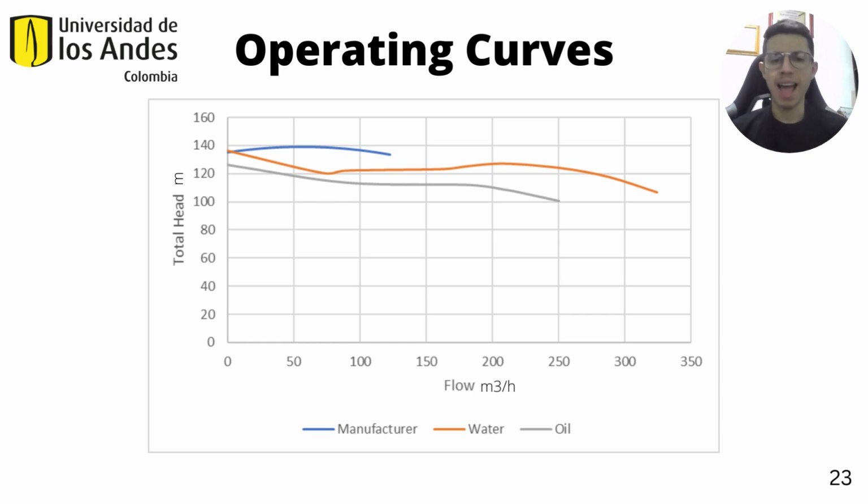On the other hand, having an axial flow, it was necessary to calculate and simulate more points at different flows. This with the objective to find the operating range of the pump, because in this range the behavior of the flow will approximate a radial flow. In addition, the aleatory errors were caused by the assumption made to find the working range, which propagate the error.